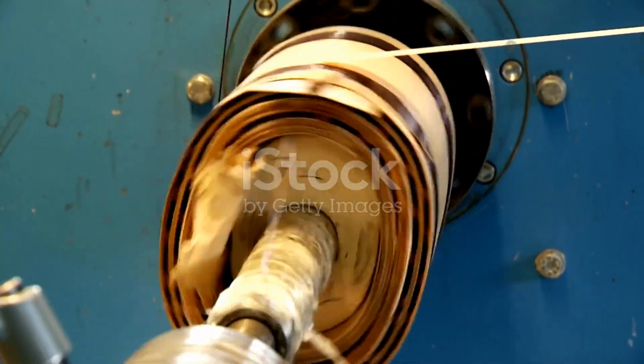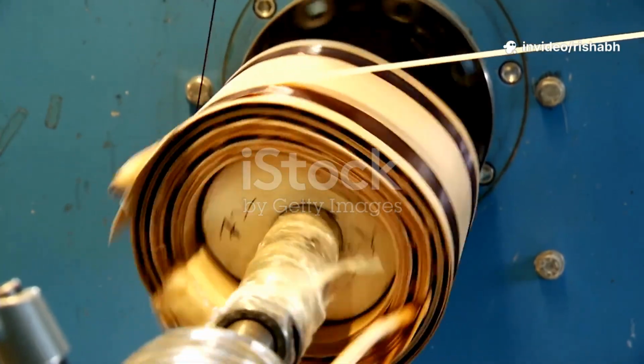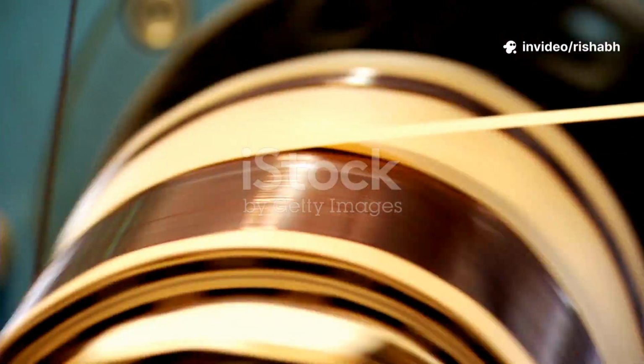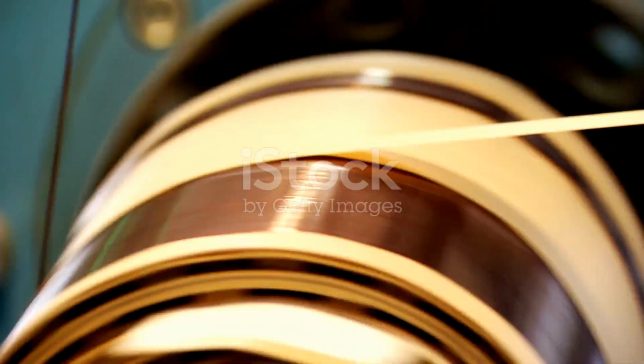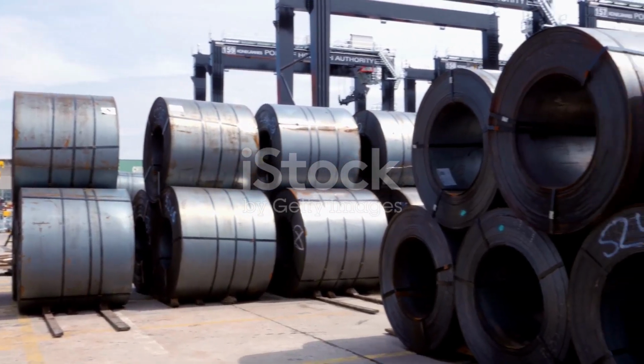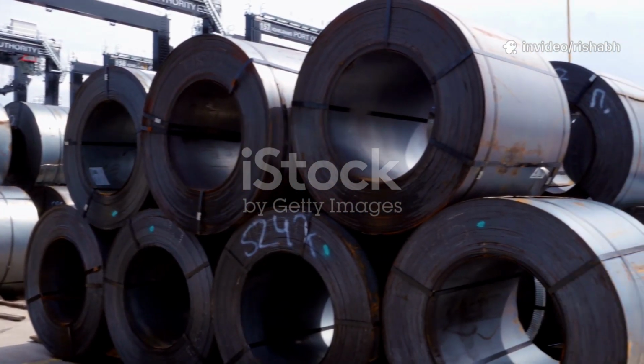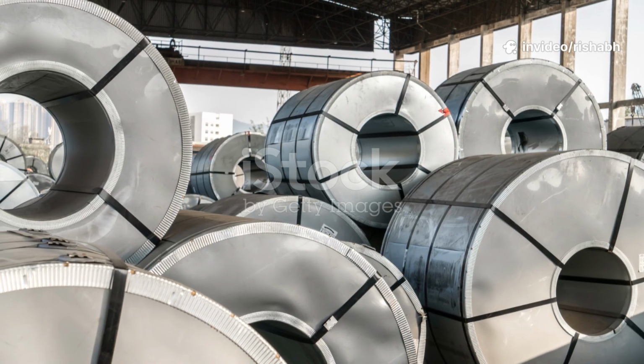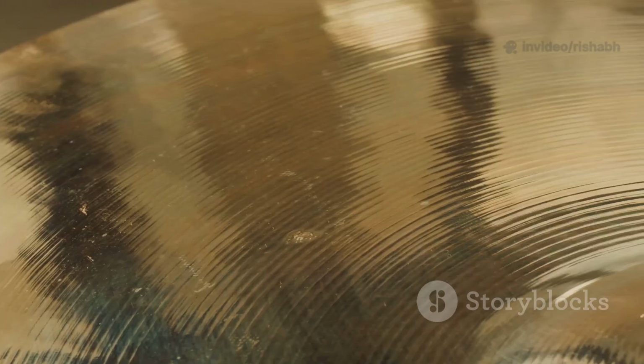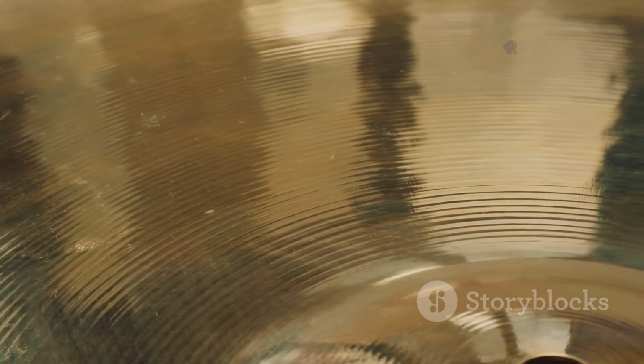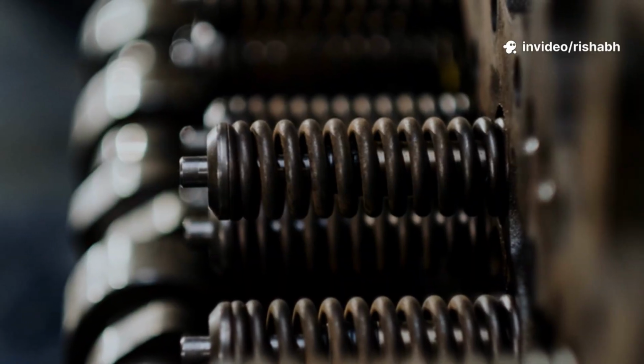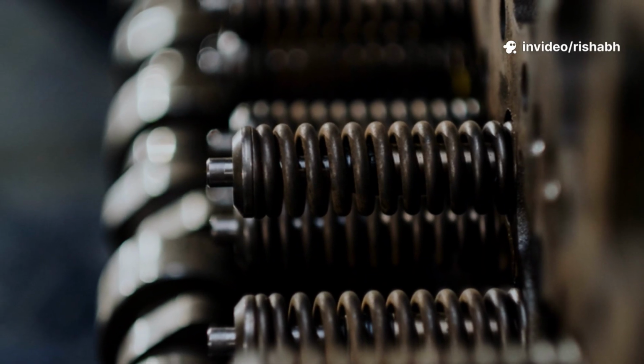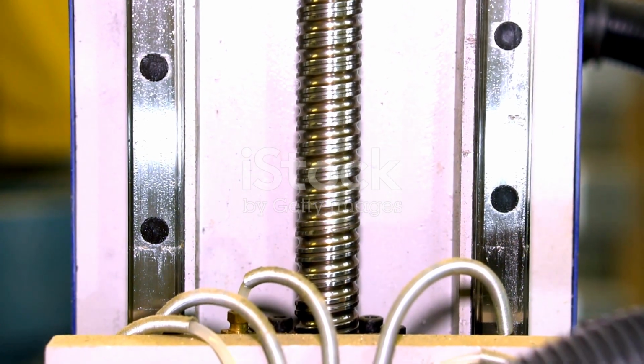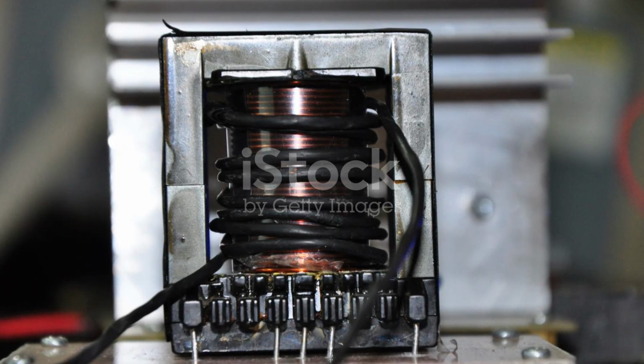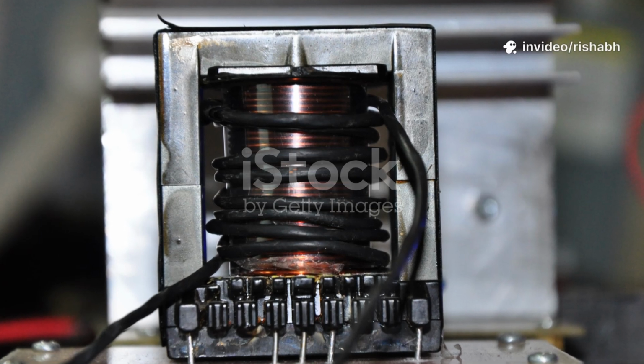Let us journey into the heart of the transformer, to its magnetic core. This is where the energy conversion truly happens. The core is not just a solid block of iron, it is a carefully engineered structure built from thin sheets or laminations of a special material. This material is cold-rolled, grain-oriented silicon steel. The grain-oriented part is key. It means the magnetic domains within the steel are aligned in the direction of rolling. This alignment creates a superhighway for the magnetic flux, minimizing resistance and energy loss. Each lamination is only about 0.23 to 0.30 millimeters thick, a delicate sheet of engineered metal.